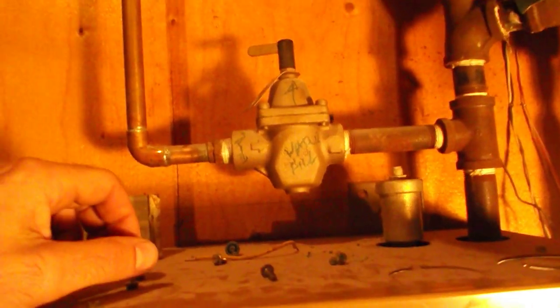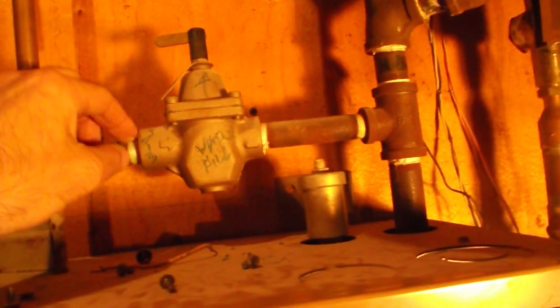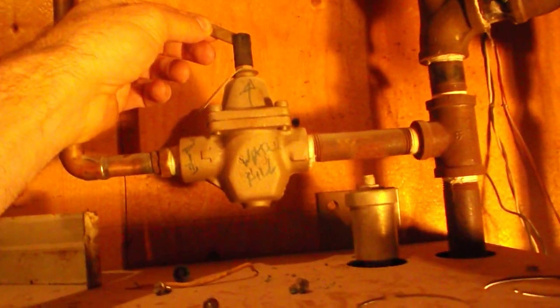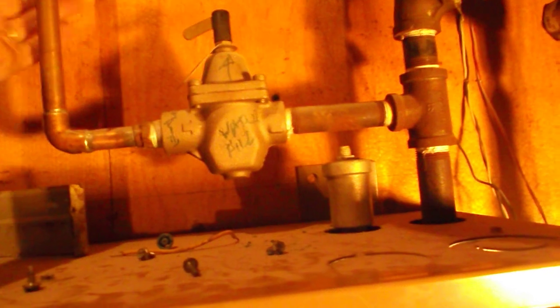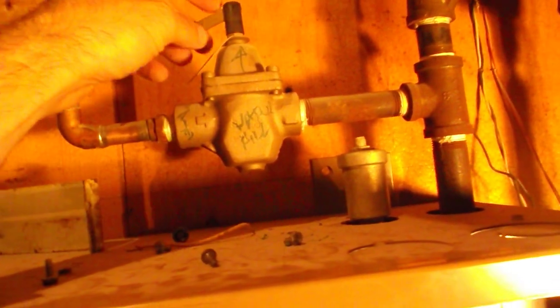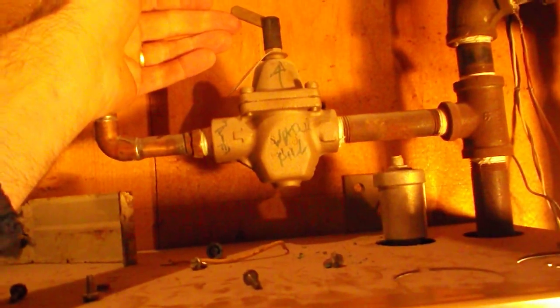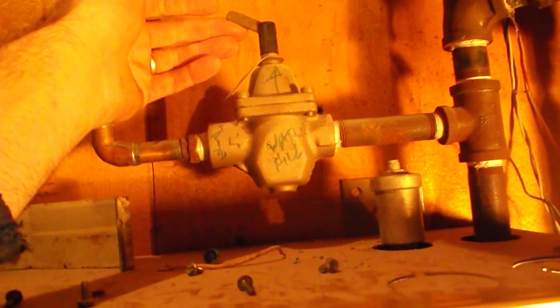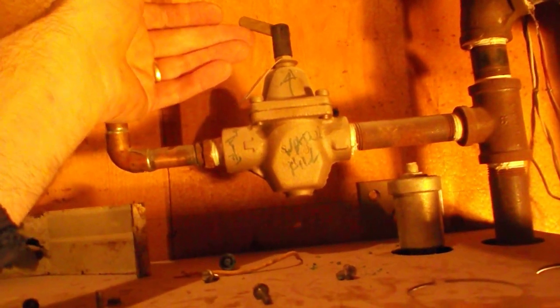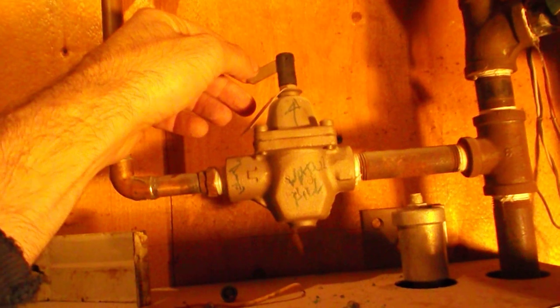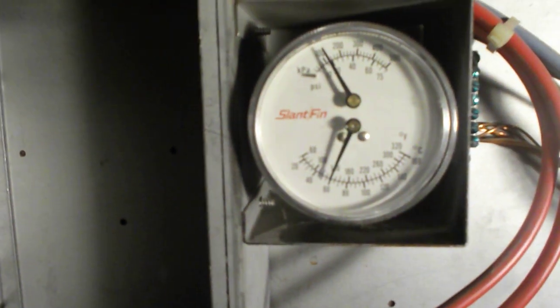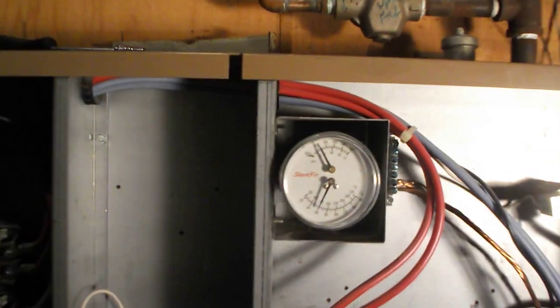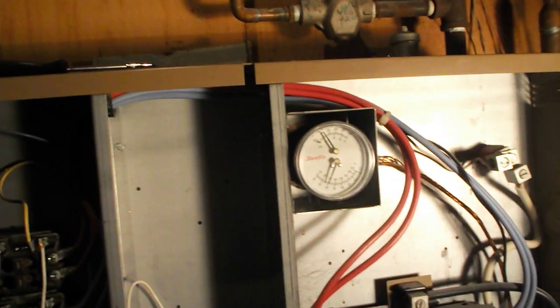But to add additional water, this line comes into the top of the boiler plumbing unit and allows you to add water from the municipal water system or your cold water system if you're well fed. And so I'm not going to do it because we have the right amount of water in now. But to add water, you either raise this lever or lower the lever. I can't remember, and I'm not going to try, but it's one of the two. So you would do that until your pressure gauge shows the acceptable amount of pressure. And again, for this unit, it's 12 to 20 PSI.